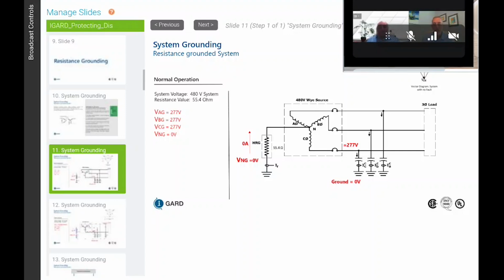So, healthy system, distributed capacitance, all these phases are 120 degrees apart from each other. The only thing that's going to happen here is you're going to add up the current from A phase, B phase, and C phase, and only the imbalance of the distributed network will come, well, it won't go through here because we're not changing the current. They're going to add up to zero because whatever load comes in here is going to go back the other two phases. This distributed current does not return back on the neutral because there's no path to the neutral. You have 0 volts at the neutral, you have 0 volts at ground, you have 277 volts. So there's 480 volts between A to B, B to C, and C to A. That's where the current is going to go. If that doesn't make sense, please email me and I'll be happy to share some more insight.